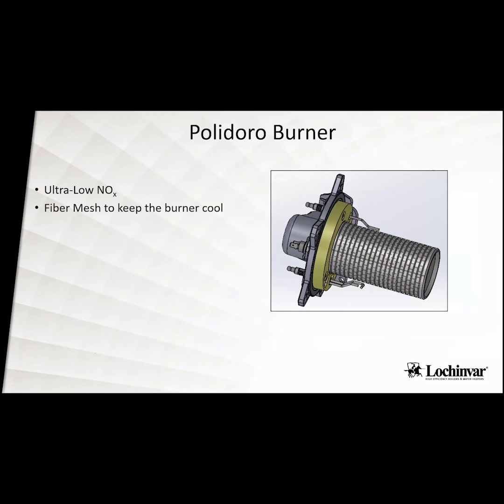All right. So the burner that we have on here is pretty much just like one of the burners that you would see through a 199 boiler. It has that fiber mesh, and we have our Run Cool technology that's built into this burner. So this burner you can touch with your hands. You're not going to damage that burner whatsoever. If any of you have been to the Lochinvar factory and seen our burner demonstrations, where they have the burner going, they shut it off and they grab it with their hand. It has that Run Cool technology built into that burner.